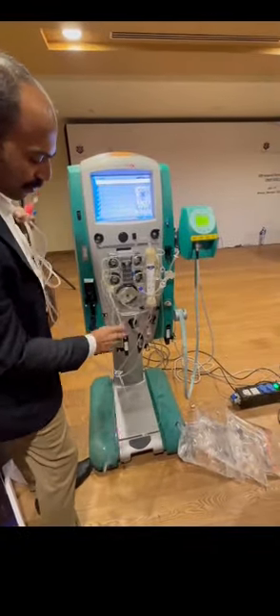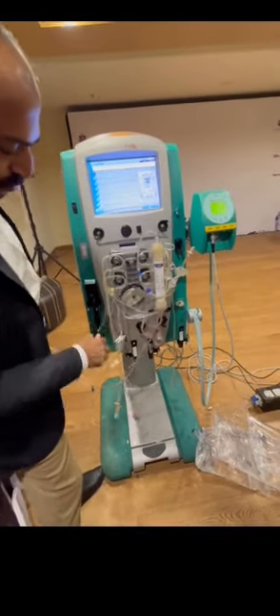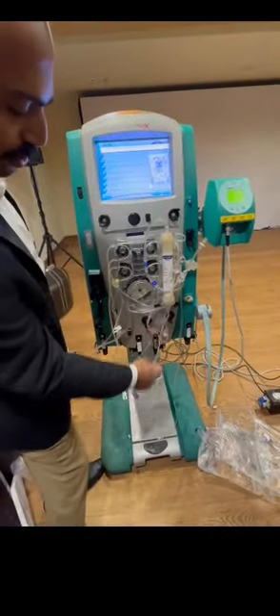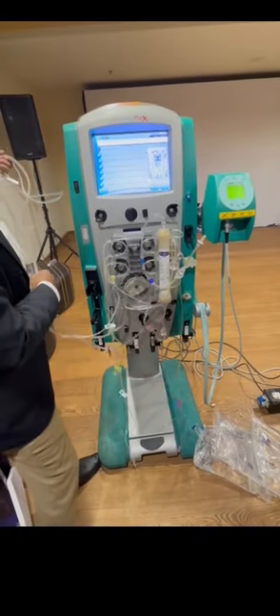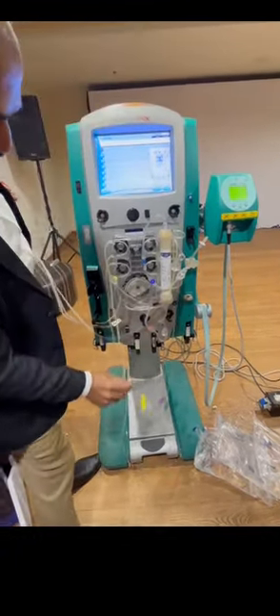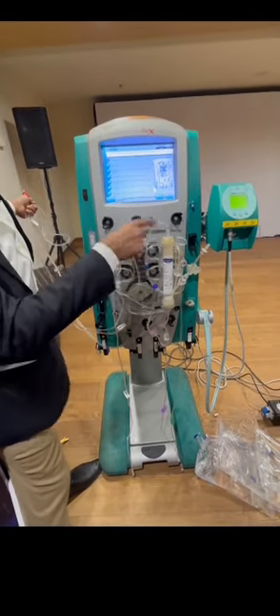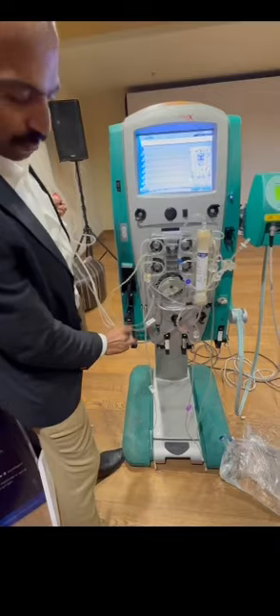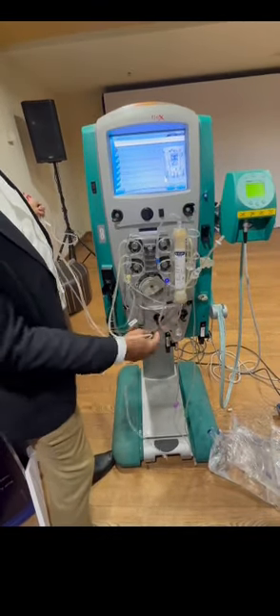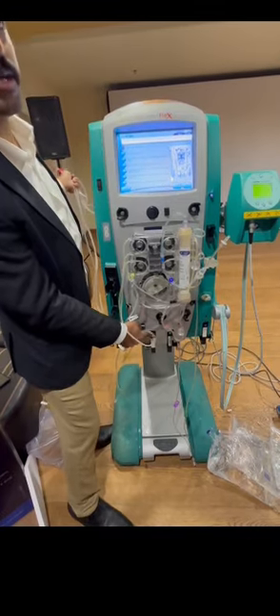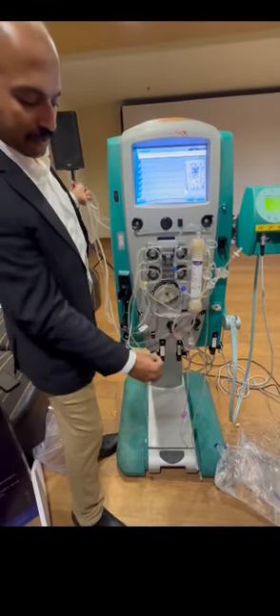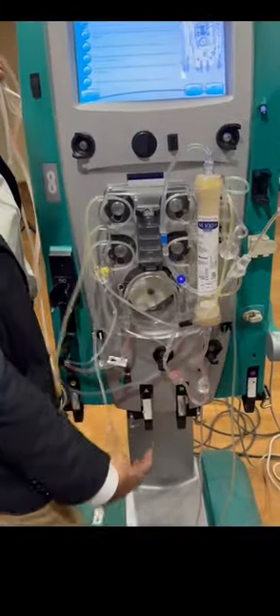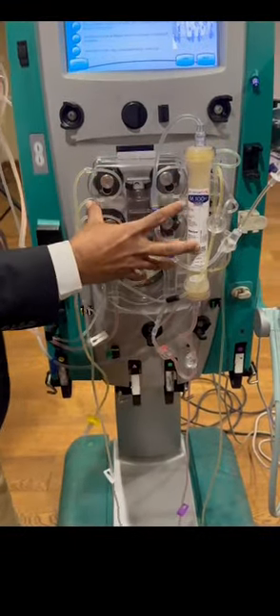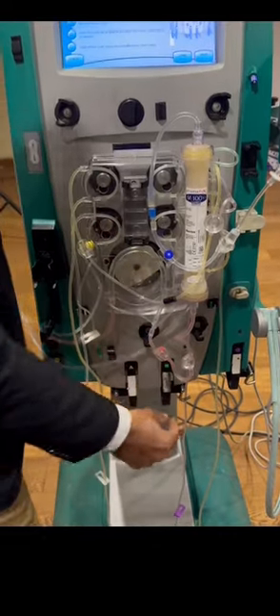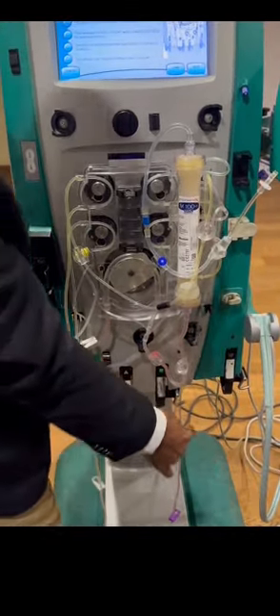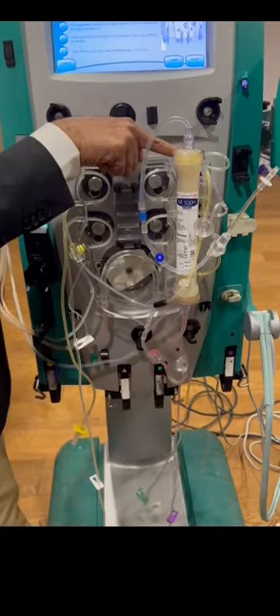Then we have four more lines with color coding. The access line is red, the return line is blue, and this one is for the effluent bag. It will collect the effluent from the circuit and drain it into the effluent bag, which is the white color bag. The white color line will connect with the pre-replacement or citrate bag. It will collect the citrate or pre-replacement from the bag and deliver it before the dialyzer. I will show you where exactly it attaches. Then the dialysate line will collect the dialysate from the dialysate bag and deliver it to the dialysate compartment here.